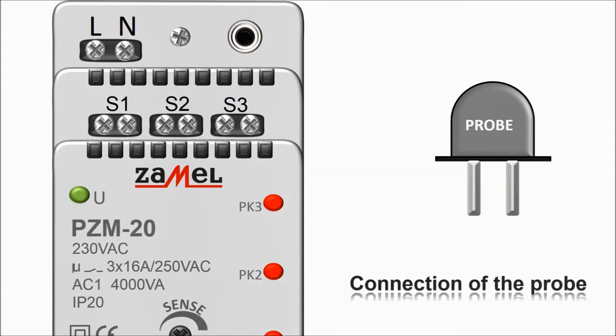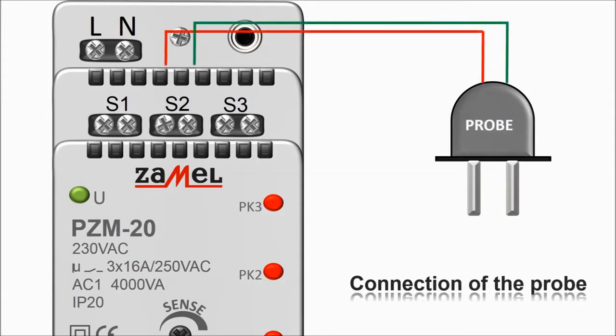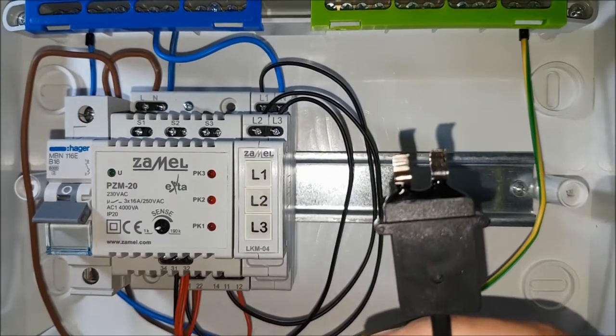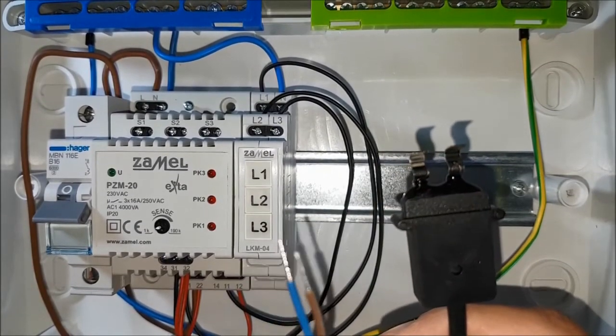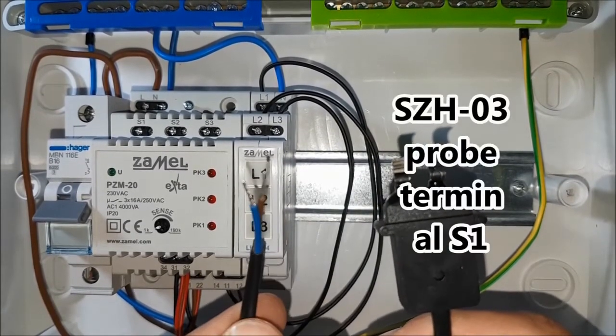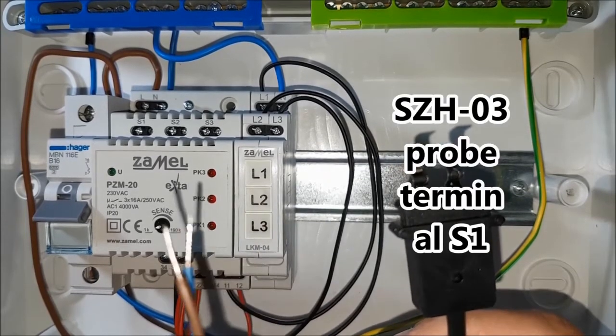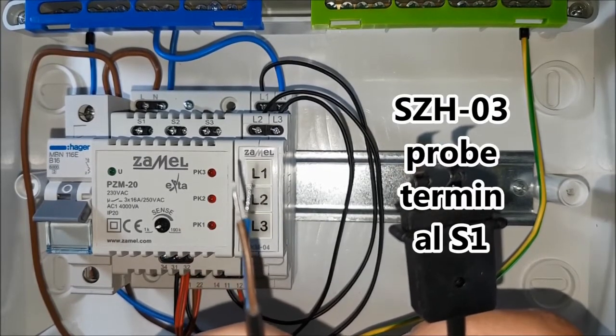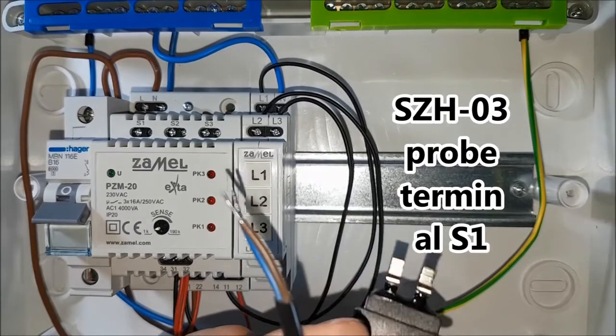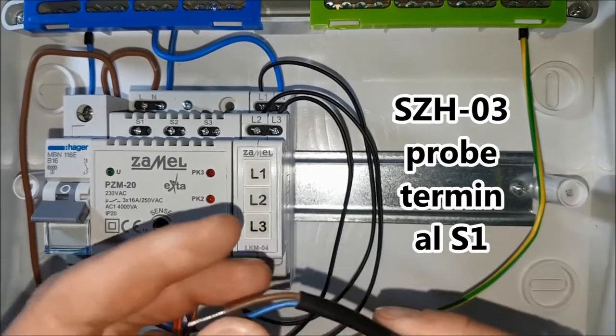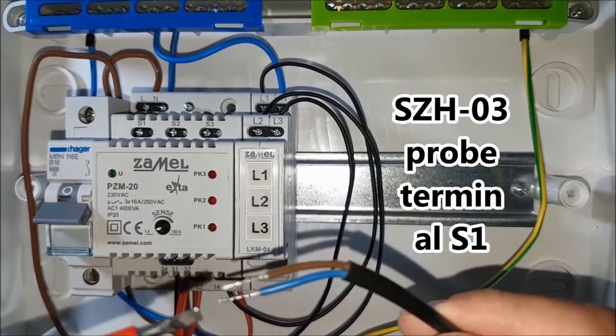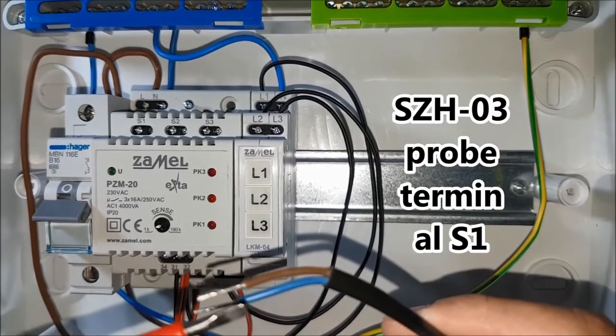Connection of probes. The probes are connected respectively to terminals S1, S2 and S3. More than one probe can be connected to a single input through a two-wire solution. It is therefore possible to connect the probes in parallel and in series. Connect the wires of the first probe to terminal S1.